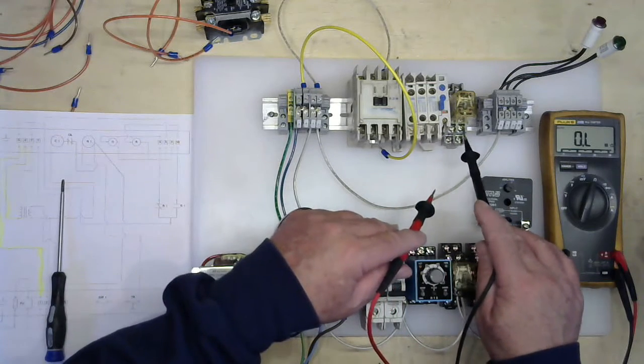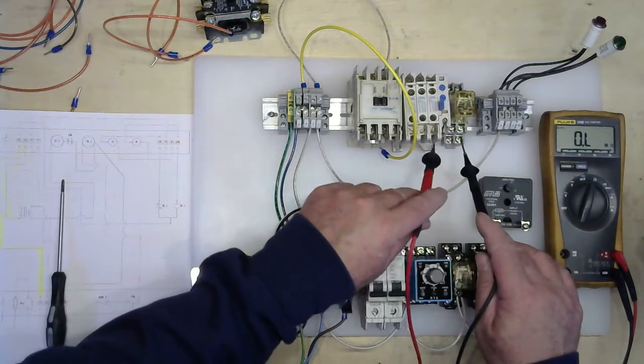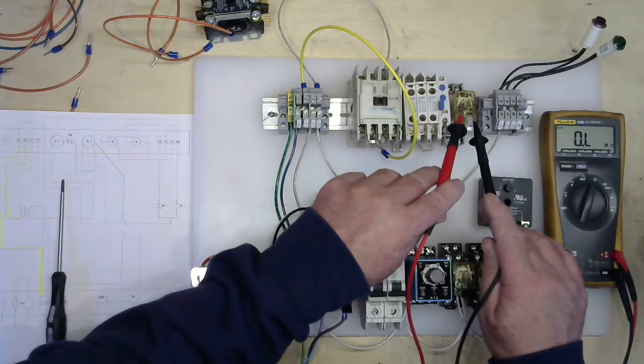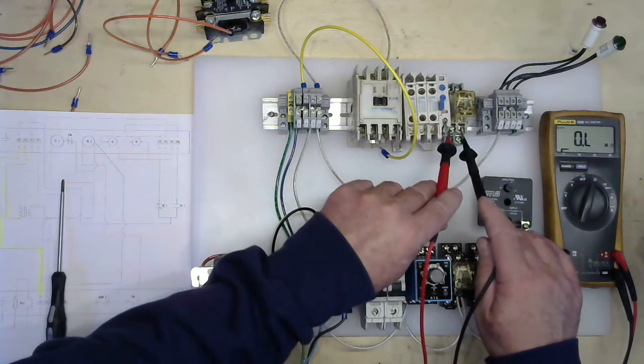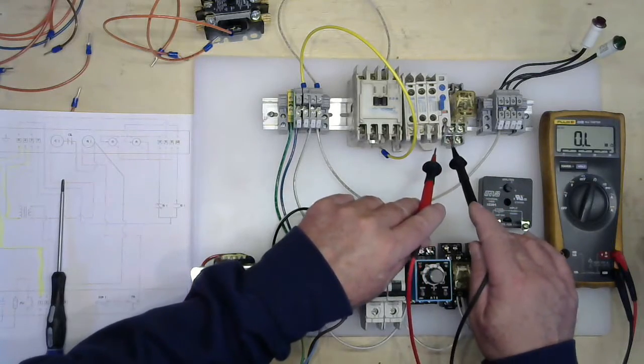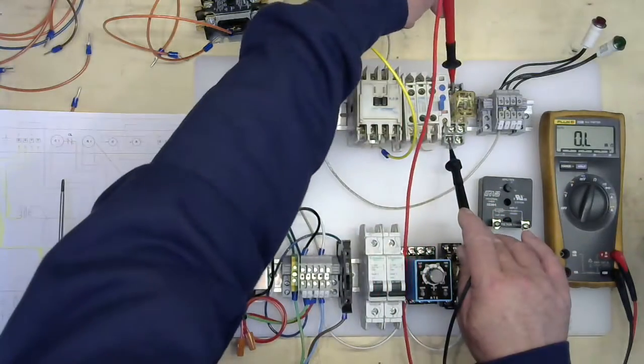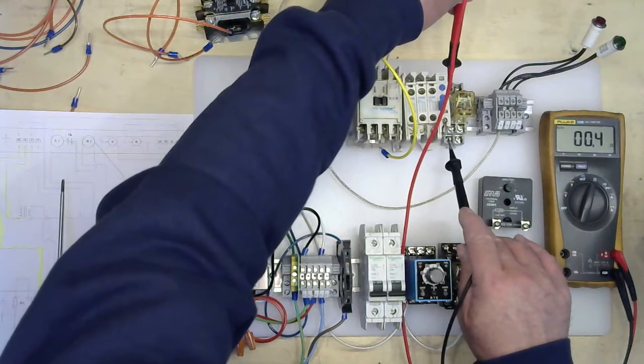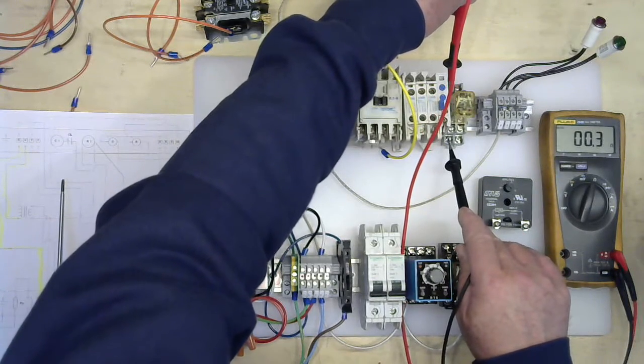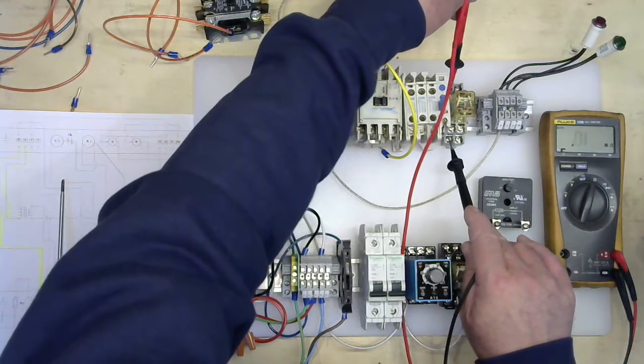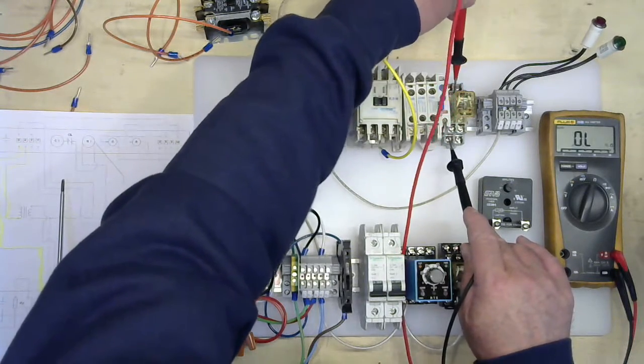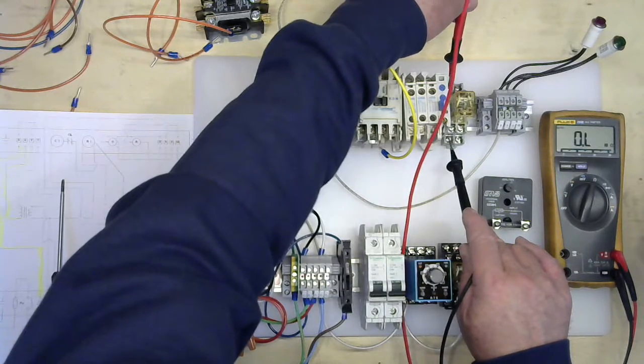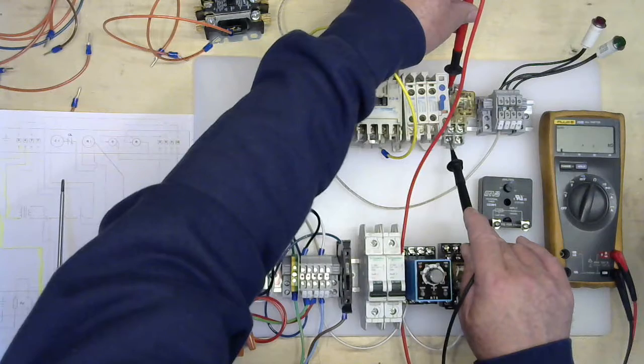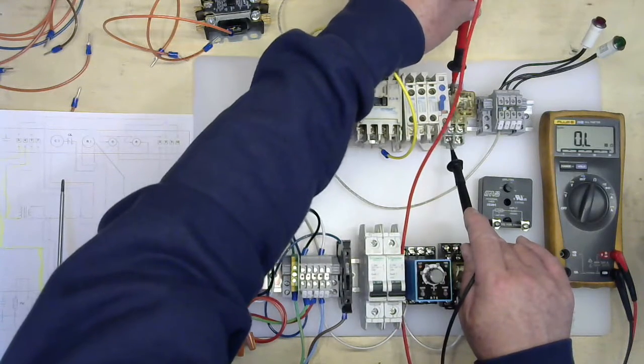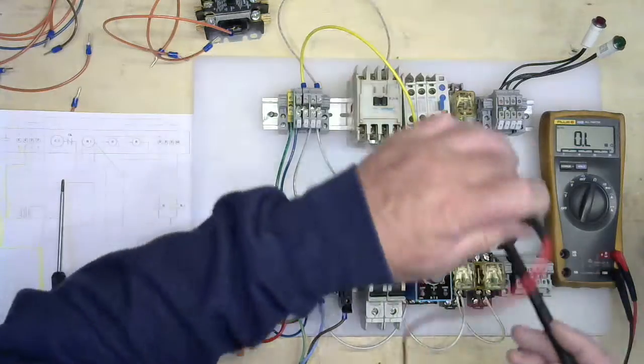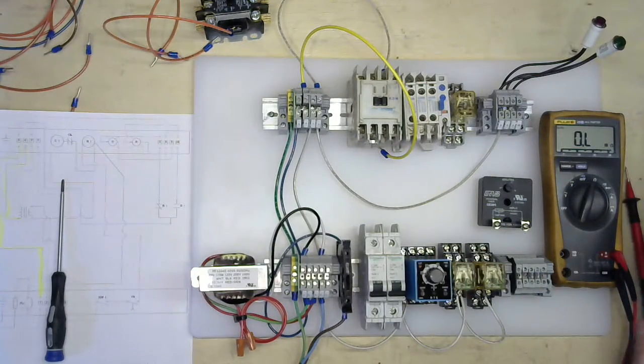So if your coil terminals are on one side, 90% of the time on dual purpose relays, your common contacts will be in close conjunction to your coil. So if I turn it on here and I start on the other side of my terminal, I'm getting 0.3 ohms of resistance. So that's telling me this is my common, this is my normally closed contact. And if I go straight down on the same common, I get open, closed, normally open, normally closed, normally open. Since I had my meter out, I know that's my connection point.